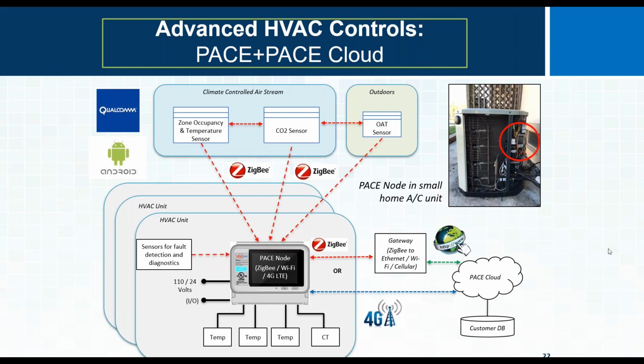So even so, you're optimizing compressor and fan operation, and getting supply and return refrigerant temperature, full power. For those who know the measurement and verification jargon, it's an IPMVP Option B compliant device, so you're getting real-time monitoring. And as Antoine mentioned, wanting to add features and options through Zigbee — an open standard wireless protocol, well standardized in the industry — you can add zone occupancy or temperature sensors, CO2 sensors, and so forth, to provide demand control ventilation. So you can build it out, but at core you're getting supply and return temperature, all going up to the cloud, being trended, with fault detection messages generated. So you're getting connectivity and fault detection as well as savings, all via the modern miracle of cloud API platforms talking to platforms — that data can go wherever it's stipulated.